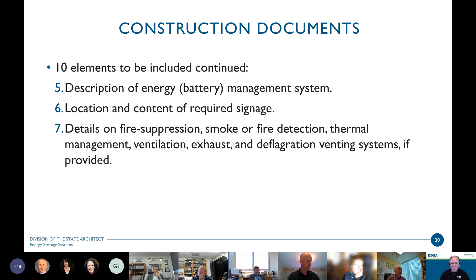The support arrangement associated with the installation. It includes the required seismic restraint. So you're going to need to have calculations showing how the weight of this equipment is being anchored to the base to make sure in a seismic event things aren't getting thrown out of whack and causing a problem. And just as an example, a 600 kilowatt system of lithium ion batteries generally equates to about 7 tons. So there's some significant load here in an earthquake event.